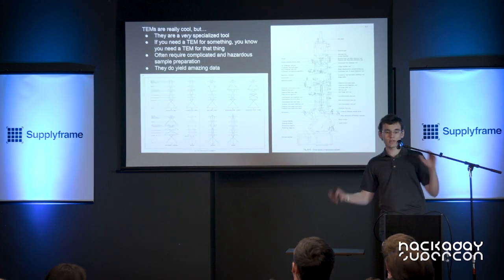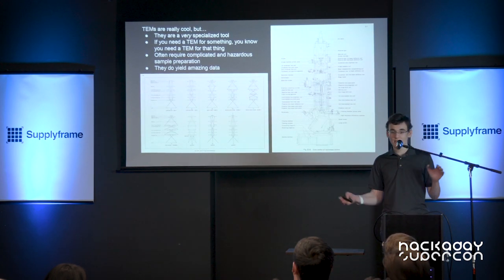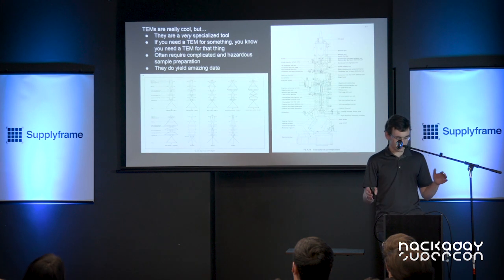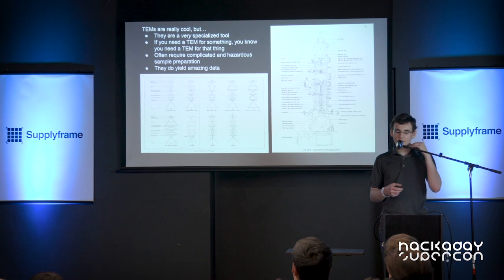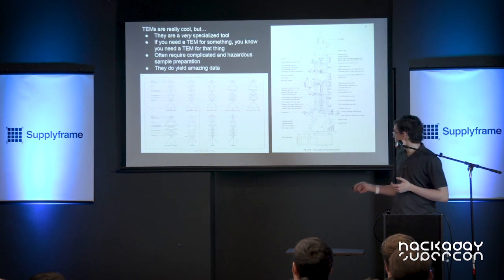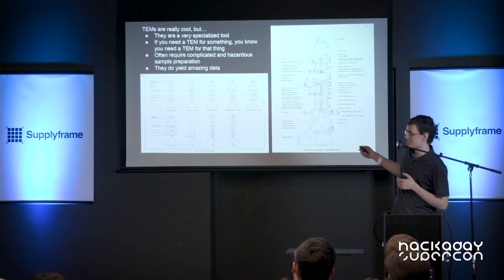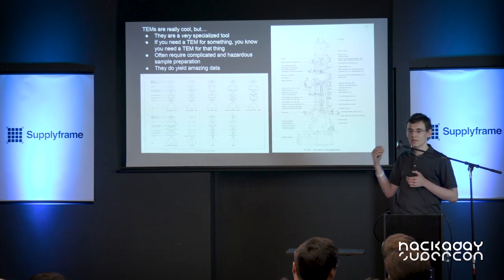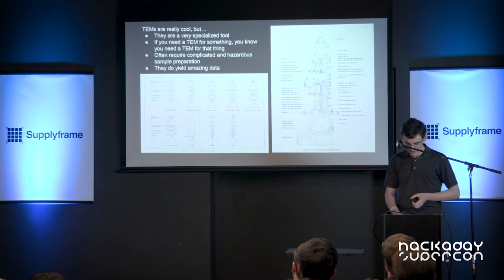Starting out with TEMs — they're really cool and amazing, but they are a very specialized tool. If you need a TEM, you're going to know that before you even start. They often require complicated and hazardous sample preparation. You have to have samples very, very thin. The data they yield comes at a cost of complexity. You have to keep image information through an electron beam through a whole bunch of different electron optics — there are 43 different electron optics inside that column. Almost every single one has to be perfectly aligned and manipulated to generate your image. So not a tool you want to use every day.